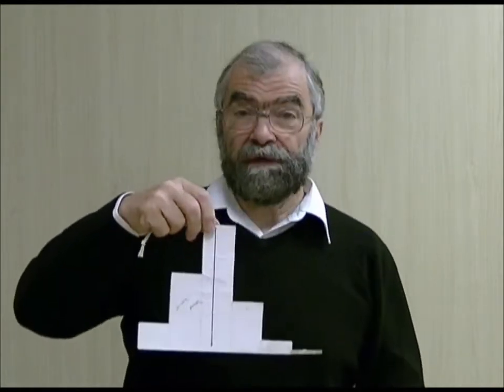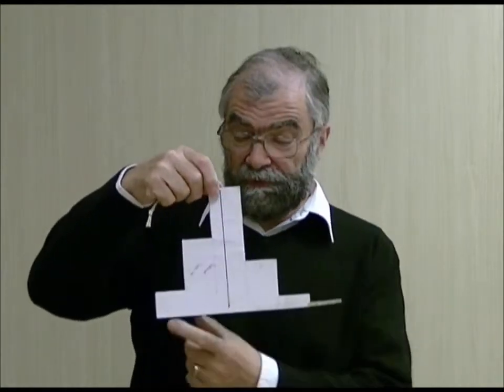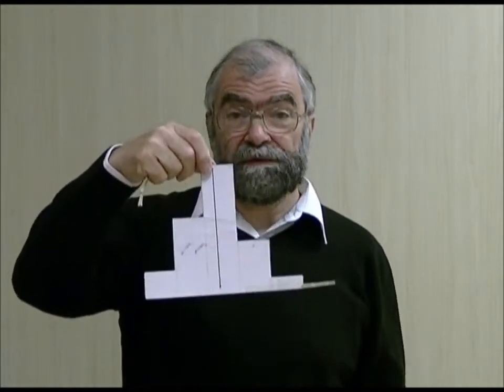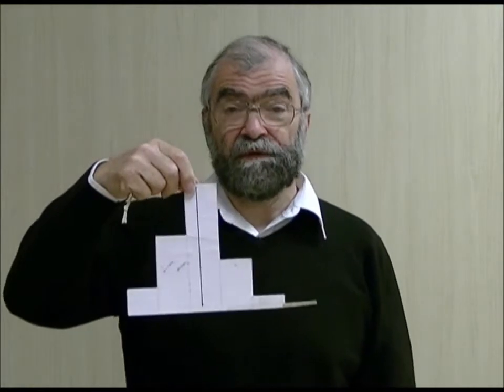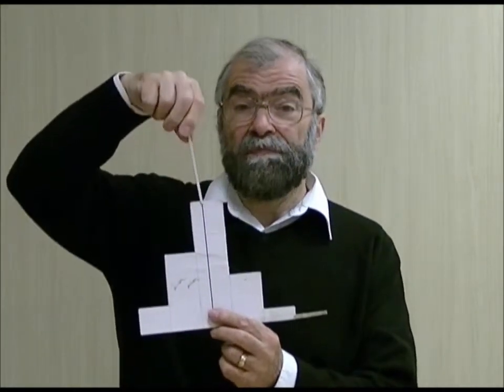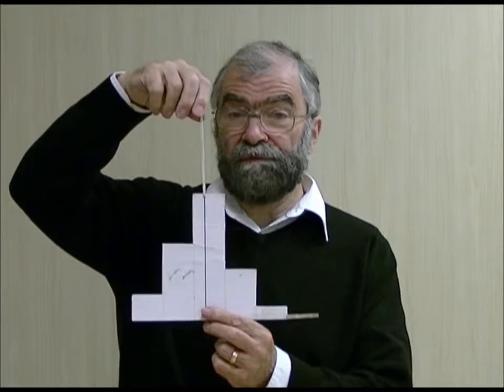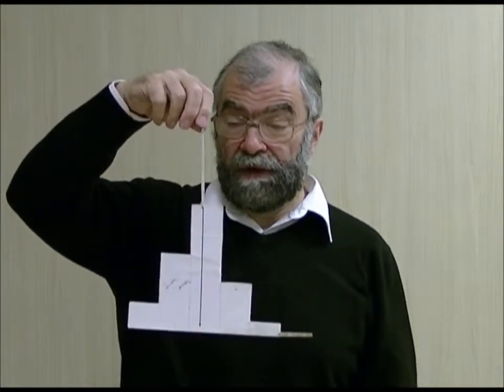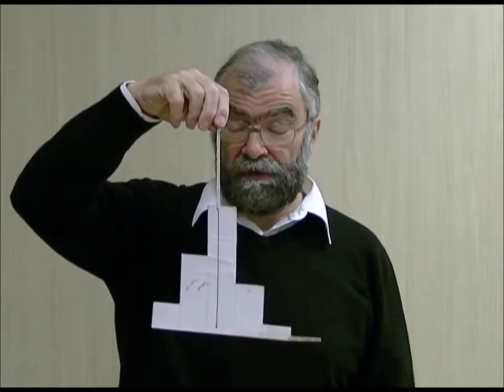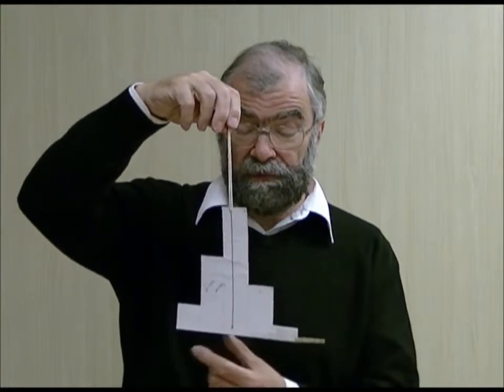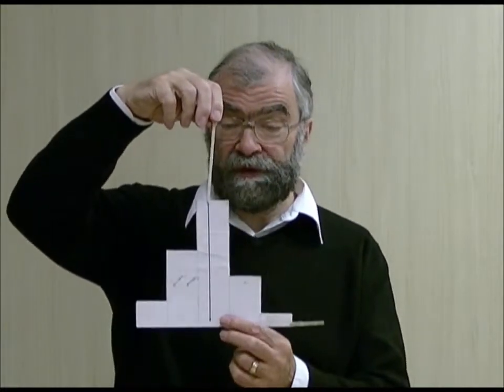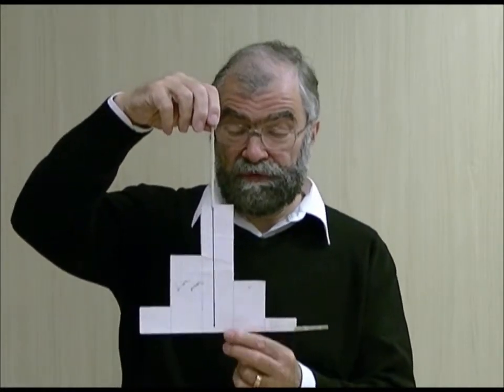If the size of the output signal from each photomultiplier tube is represented by the height of each of these blocks on this cardboard cutout, then the balance point, or the centre of gravity, is our best estimate of the correct location where the gamma-ray occurred. So we need to find the centre of gravity, or the centroid, of this distribution.